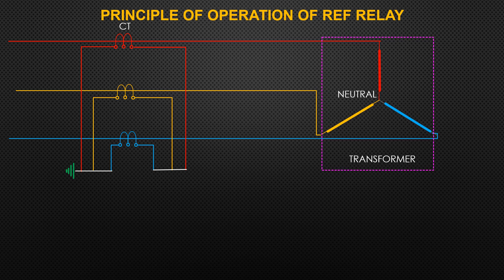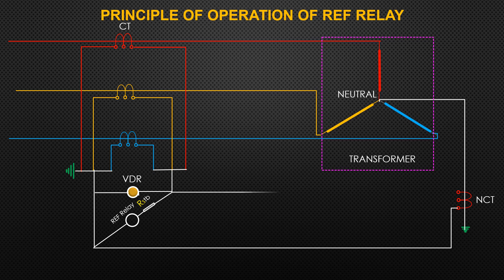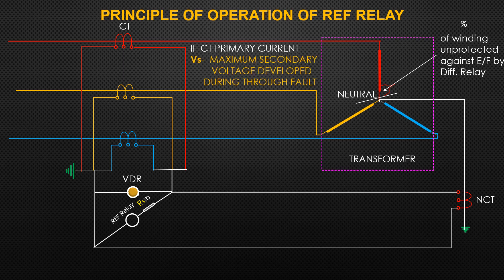Saturation of CTs makes the situation a little more complicated. The stabilizing resistor guarantees that the relay will not trip during a through fault. The VDR (voltage dependent resistor) feature is to protect CTs and windings by limiting voltage during heavy inside faults.